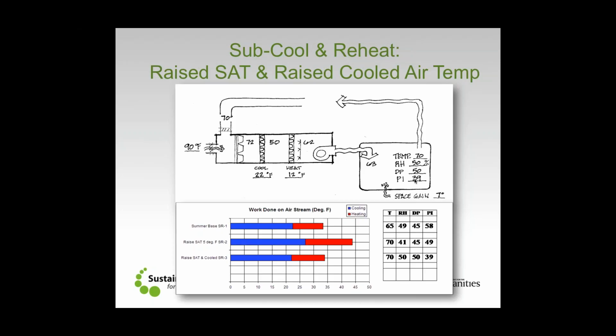Well, yeah, whoops. Start going back through and running the numbers, right? We've got warmer air coming back, blending with 90 degrees. And now, even though we're only doing 50 degrees, here we are. We're doing 22 degrees worth of cooling to achieve that 50-degree dew point. But still, in order to get to 70 degrees, we have to add another 12 degrees worth of reheat to get it up to the supply air temperature that we have to have.